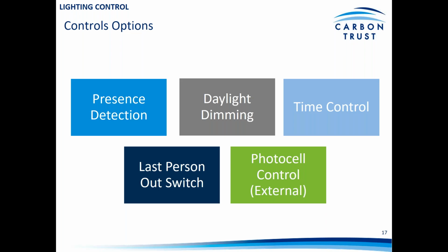That can also be achieved using a last person out switch. So having all the lighting systems in the building set up to be switched off with one switch is an easy way to switch off all the lighting at once, rather than have somebody walk around the entirety of the building to switch off individual lighting circuits. And indeed, for external lighting, the use of photocell control will pick up on the level of daylight and switch off lighting when it's not required at night, and that obviously will track the seasonal change in daylight as well.